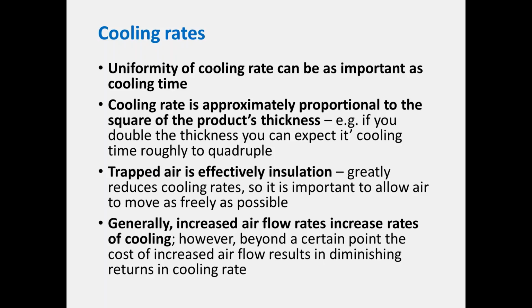If you increase the thickness of your product—and I mean the effective thickness, so if you have a whole lot of different cartons stacked together—you don't just double the time if you double the thickness. It goes up by more than a factor of 2. That's why in a carton freezer you always want them exposed on all sides. Really, if you must improve your cooling rate, under some situations reducing your package size may be the only viable option.